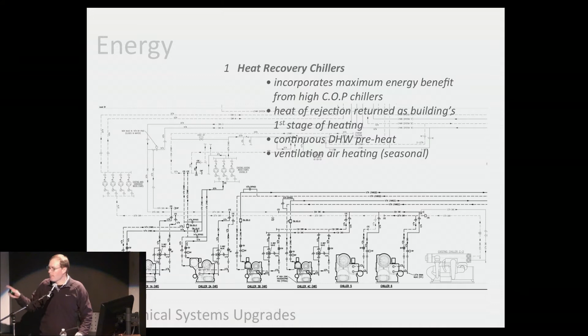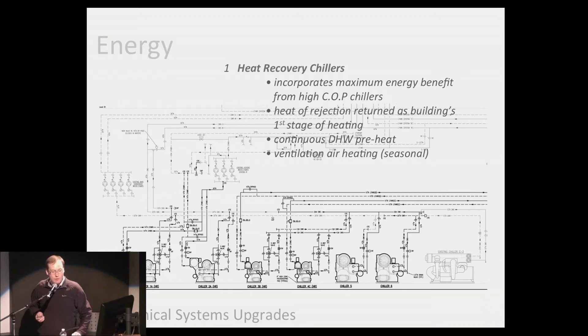One of the big things that we discovered was that the original design for the mechanical system actually wasn't installed. The original design had heat recovery chillers. A typical building has a chiller, takes the heat out of the building, sends it to a heat rejection device, a cooling tower, and consumes electricity to power that chiller. What we do here is the chillers remove the heat from the building, but the building ventilation system is an induction system. It requires a primary heat source. So instead of sending the heat directly to the cooling towers, we're putting it into a primary thermal loop. So already we're increasing the efficiency there.